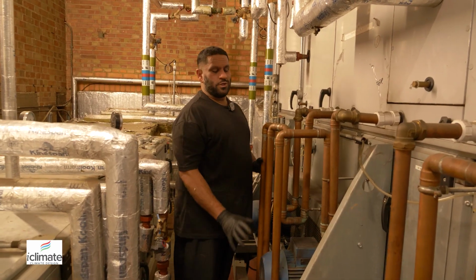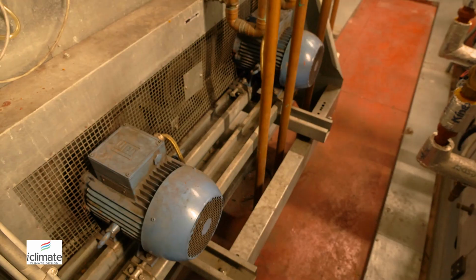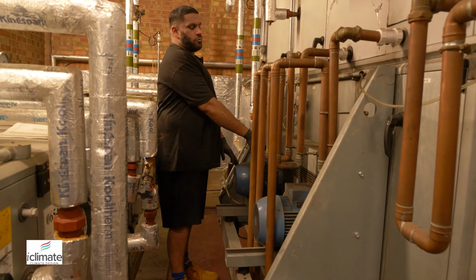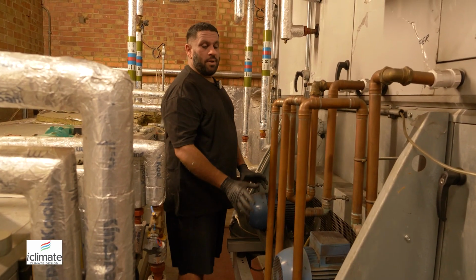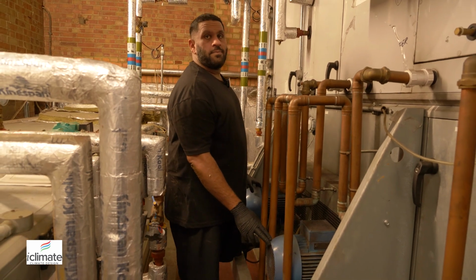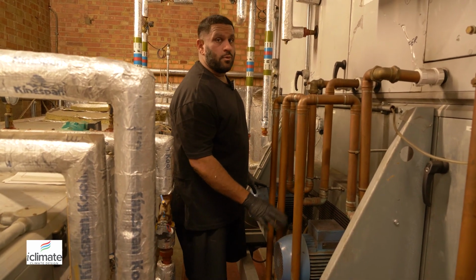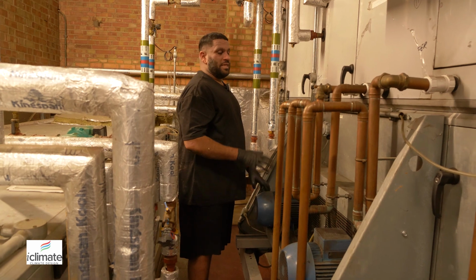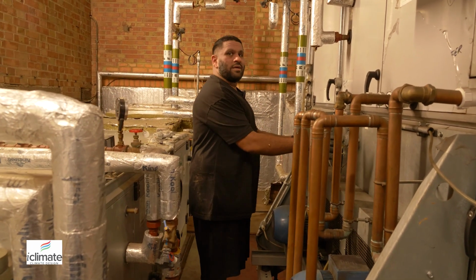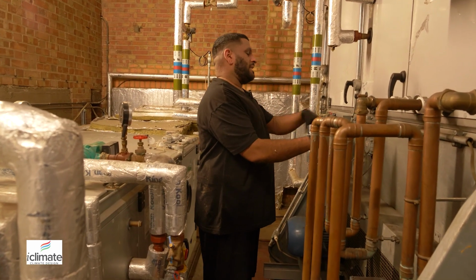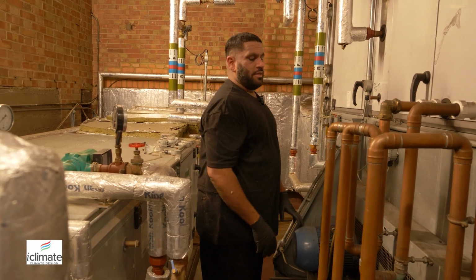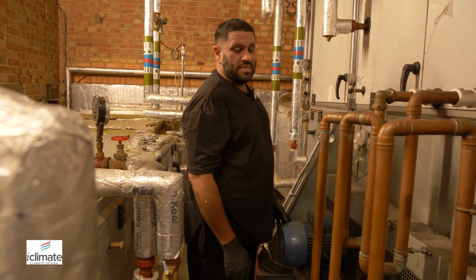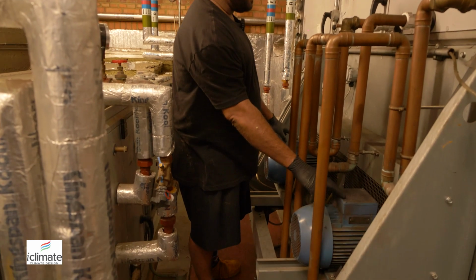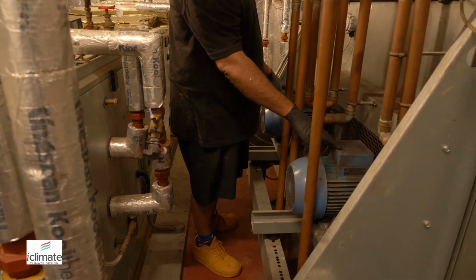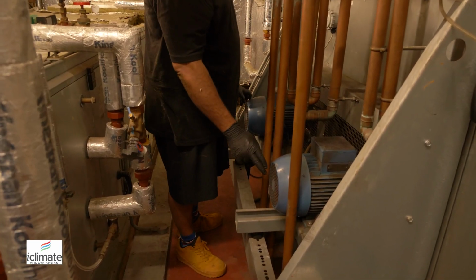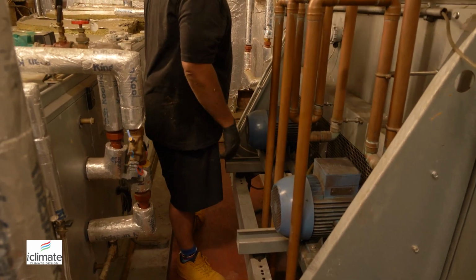This is a very old air handling unit, right? So that's why we've got the pumps sitting outside, and they're belt driven to the central fan pulley. So this is in case one pump fails, there's another, a backup pump to carry the air handler, ensuring minimal downtime, right? This is really old technology. These days, like you saw in the chiller, it's all in the compartment with the motor and the belt attached to the mechanical fan, but this is all outside. I guess it provides an ease of maintenance and checking as well. So you can check everything while the fans are running, from the motors, current draws, amperage draws, RPMs, and anything like that.